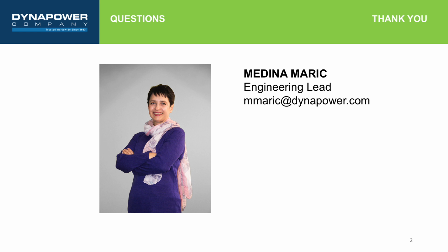So, two very separate issues. Let's take power factor first. As was mentioned in the presentation, SCR units are typically considered a current source and choppers are considered a power source. What that means in essence is that to regulate an SCR unit, you control the phase angle of the SCR. When you retard the phase angle of an SCR unit, you reduce the power factor.